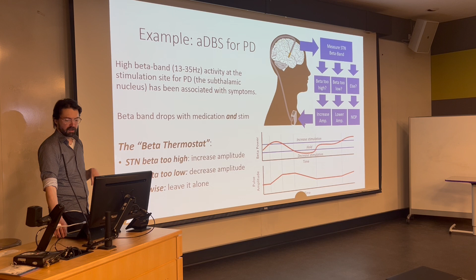And so it's a very simple way of using this almost as a thermostat, where if beta's too high, you need to turn on the heater, you need to give it some more juice, some more stimulation. If beta gets too low, we're probably overstimulating, so we can relax a little bit. This is an example of a very simple algorithm, which is also effective in terms of providing a way for the device to balance stimulation as medication washes in and out. Now, the ongoing trial by Medtronic, with the FDA approval, has shown that this actually works and provides a better benefit than off the shelf.